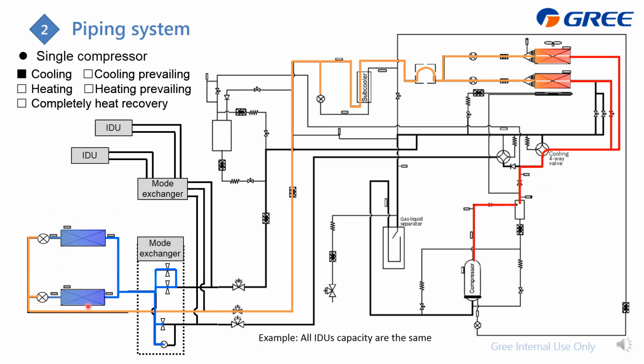Then it becomes low pressure and temperature gas, and then flows into this gas pipe and then to this mode exchanger. And here just pay attention that at this heat exchanger, as it needs to go back to the outdoor unit, it is only from the low pressure gas pipe, which is this one, and here we just make it conduct, and then just connect to the low pressure gas pipe, and then make it go back to the gas liquid separator. And after the liquid part is separated, only 100% gas will flow into the compressor for compression.